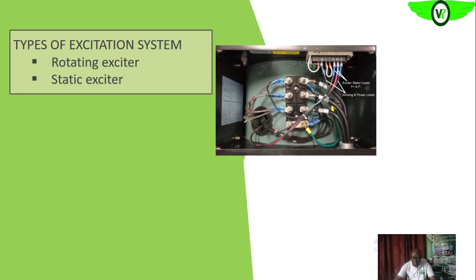The input to it is also gotten from the output of the generator, as you can see here. This is one of the legs, and then there is a connection to one end of the output, taken from phase to phase, the middle of it. So if we have 415 volts phase to phase from the output of the generator, the middle connection will give us 220 volts, which is now fed to the AVR.